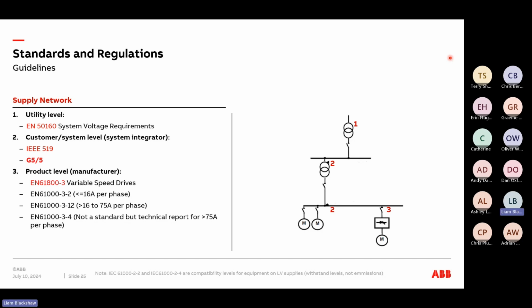So the limits for harmonic distortion are always defined by national or international standards and recommendations. It's down to the DNO. They're responsible for ensuring the system voltage requirements are met at the utility level, but it's them to enforce it to the end user as well. So when we look at it from a system level, they need to enforce it to their end users to say you need to be within a certain level. And what they will always tend to do is say they need to meet G5/5, or in some cases, because you may not have the right kit or the necessary kit to measure that, they might just say we can adhere to the previous standard, G5/4, for instance.